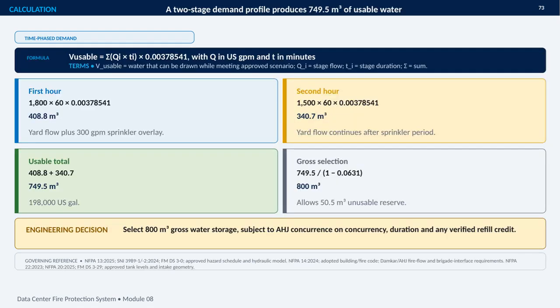This slide converts the time-phase demand profile into a usable water storage requirement. The formula sums each stage flow multiplied by its duration, then applies the conversion factor from US gallons to cubic meters. The key result is 749.5 cubic meters of usable water. During the first hour, the combined demand is 1,800 US gallons per minute for 60 minutes. That produces 408.8 cubic meters, representing yard flow together with the 300 gallon per minute sprinkler overlay.